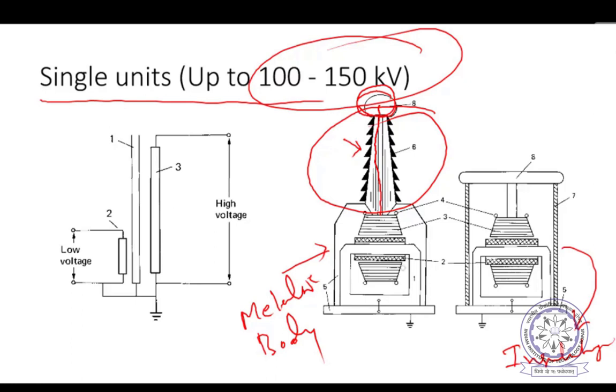This is not needed here because this body is an insulating body, already insulating. So you can simply use a high voltage electrode like this, by connecting it to the high voltage winding. This is the primary winding, and this is the secondary winding. Primary winding and secondary winding, one above the other, in order to reduce the leakage. Then there is just one leg here. This is the core, and inside this, oil is used. It is called transformer oil. It is actually petroleum based oil. Similarly, in this transformer also the same oil is used.